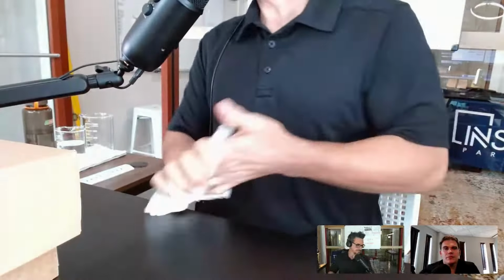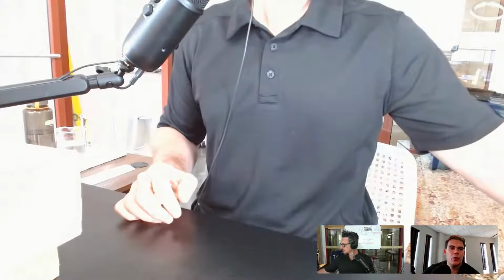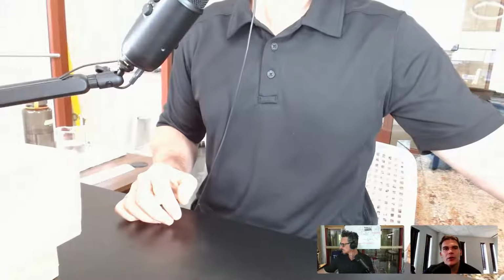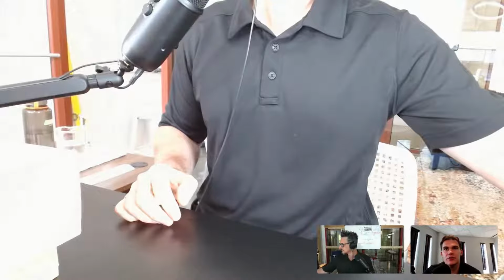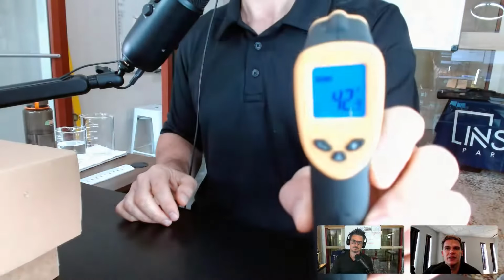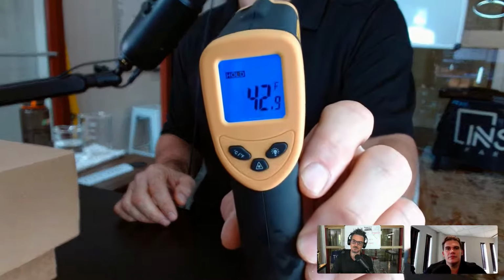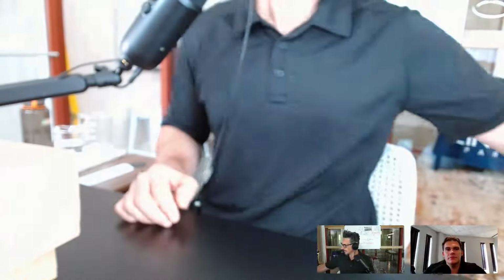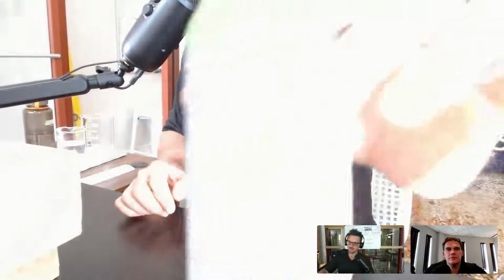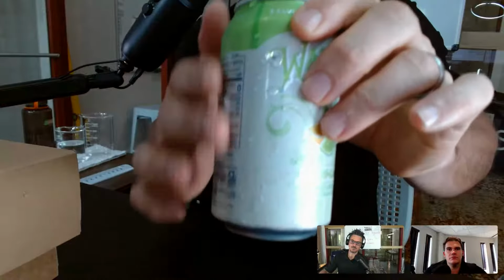We do remove humidity with desiccants as well. It also shows a good example of why we don't want thermal losses through ductwork. That's why we're always insulating our supply ductwork, right? If we're supplying 55-degree air, anything that touches it that's above that is going to condense. Absolutely. And that's the temperature of the can, 43 degrees. I think it's actually colder than that. I'm not sure how accurate this is, but you can see it's already starting to have a ton of condensation on it. Okay, that's the dew point example.